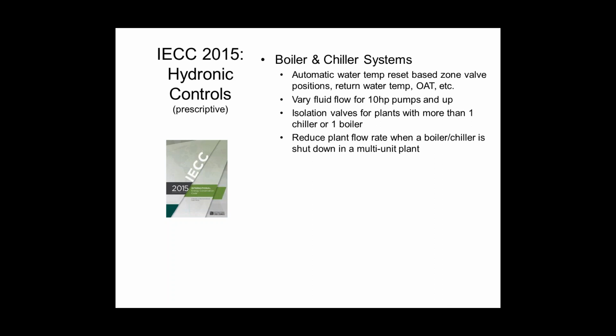If you have chiller plants or boiler plants that have more than one chiller or one boiler, I guess you're going to call it a plant, you probably have more than one, you have to have isolation valves that stop the flow of water from going through the machines that are off. It's obviously somewhat of an energy waste to do that. There are exceptions for that. If you have chillers in series, you don't have to do that, obviously. But if they're in parallel, you do need to shut off the flow to a chiller when it's not running. And then not only shut it off with the isolation valve, but then you also have to slow the flow down, probably based on a variable speed drive, right?